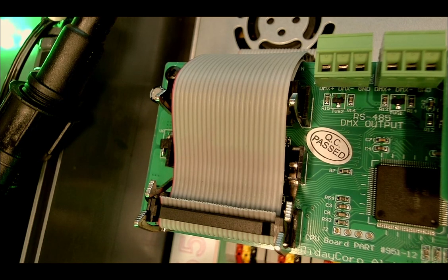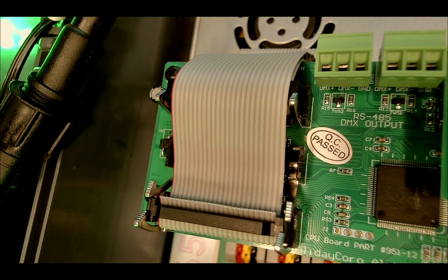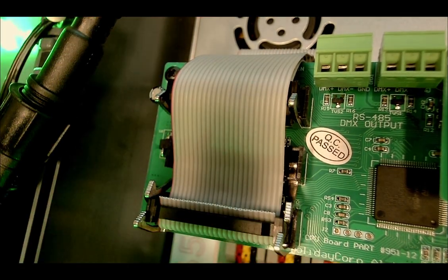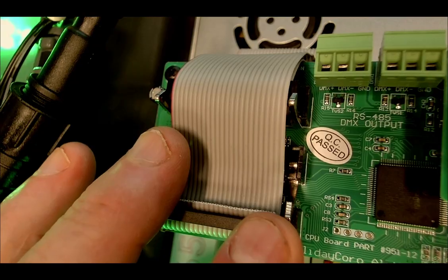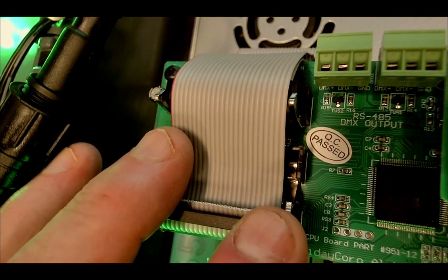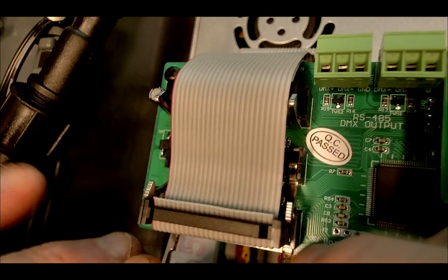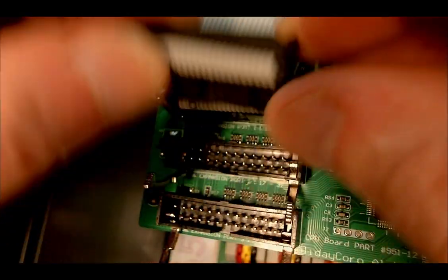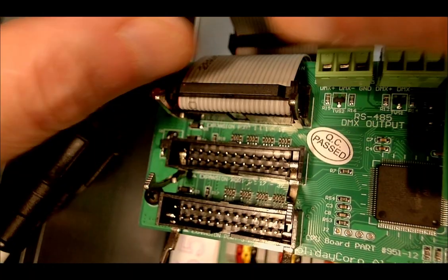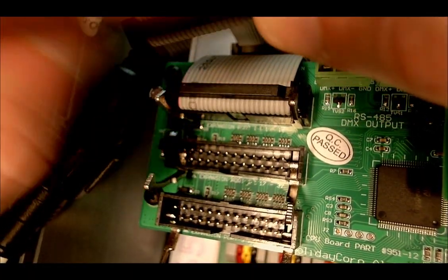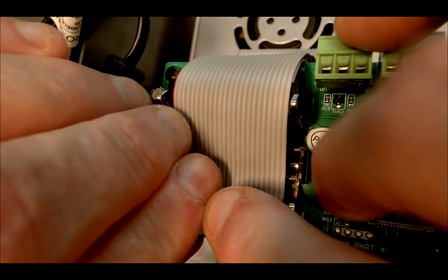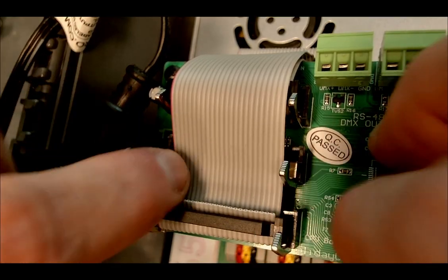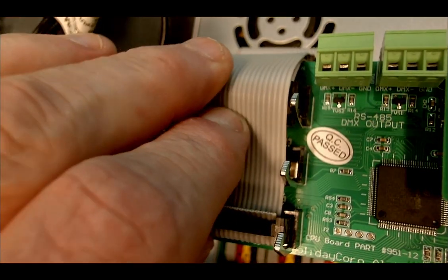Now, you can go in and reseat this. You never want to remove these ribbon cables while the controller is powered on. Always power off the controller. And in this particular case, we'll go ahead and just unplug the power. And we can go ahead and pop these levers forward and lift the ribbon cable out of place. And if you saw any kind of misconnection or anything like that, that would be an indication that there's a problem. And then we can just reseat it. Make sure that these hooks that hold the cable into place are fully seated.